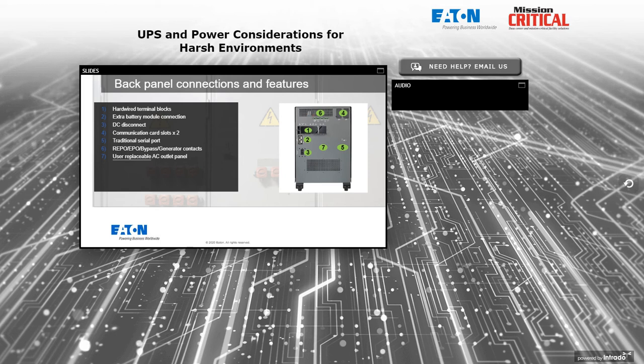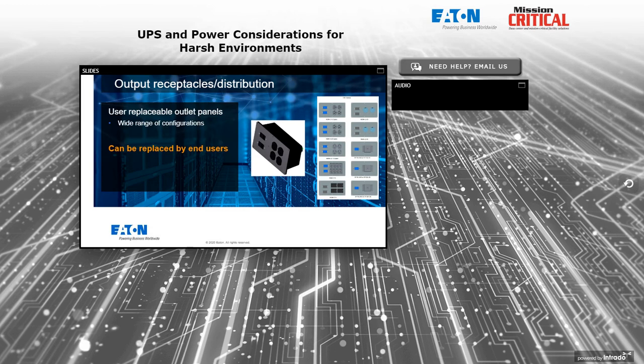And then for flexibility in the application, for the output of the UPS, it's great to have an output panel that can be removed and replaced by the user, and where the user has the choice for what receptacles and circuit breaker sizes they need. So on a UPS this size, traditionally a little bit too big to come with receptacles on the output. But if you can arrange for that and have it something where the user can select those in advance or change them if their needs change down the road, that becomes a very helpful feature and improves the flexibility and, frankly, the longevity of the UPS in that application.